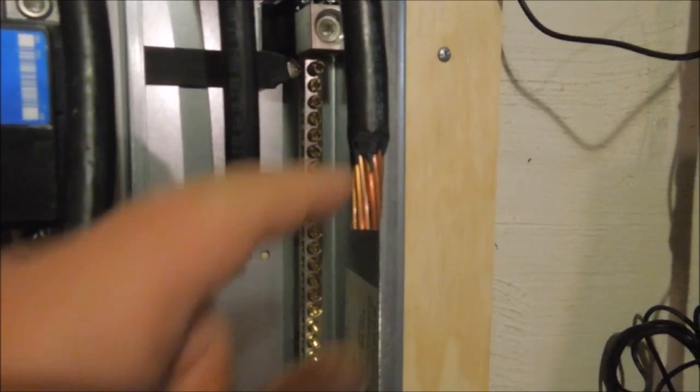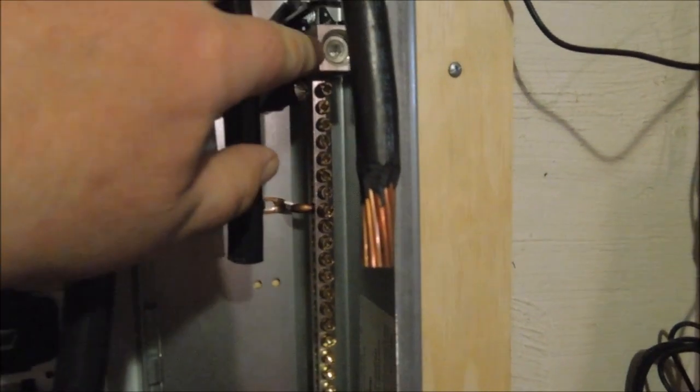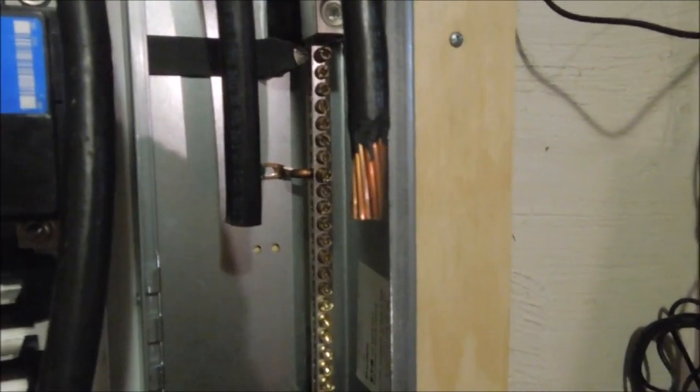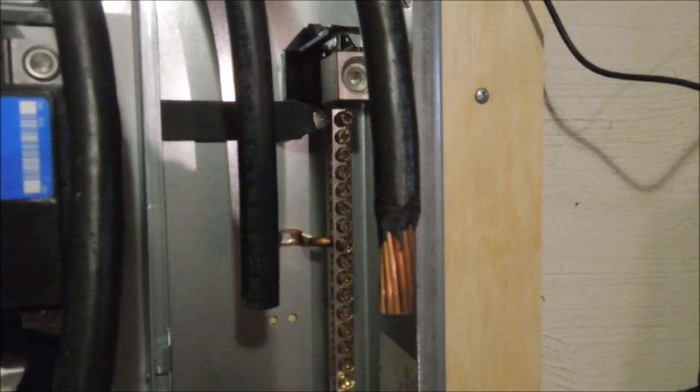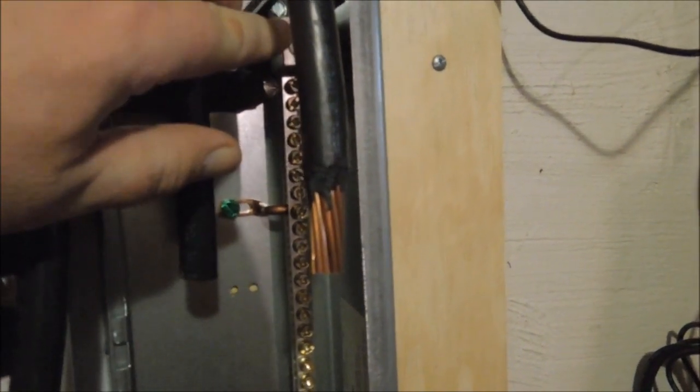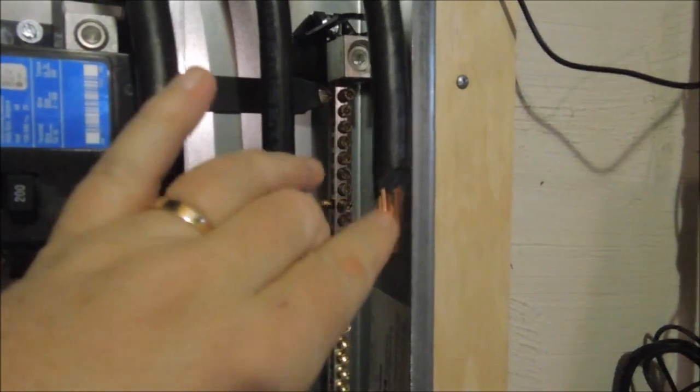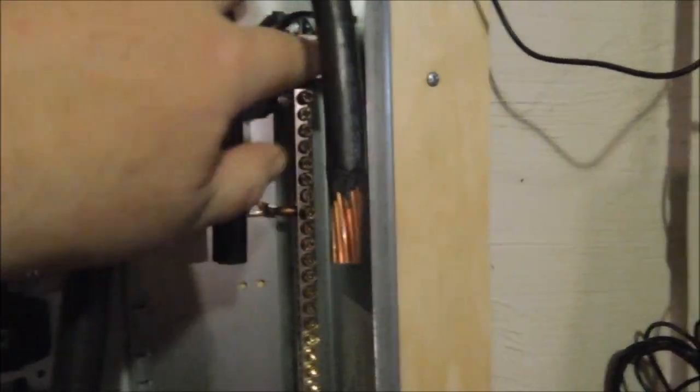The idea is that you want to strip this down far enough so that when you put it into the neutral connector, a little bit of the copper shows out the bottom so you're sure you've got the wire fully engaged. If you don't have a good connection at this point, you can generate a hot spot. So you always want to make sure that this connector is clean and fully engaged.